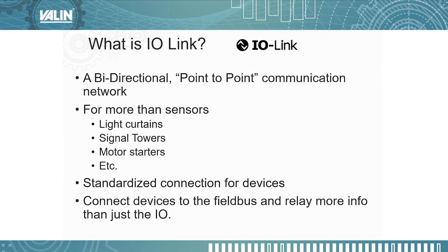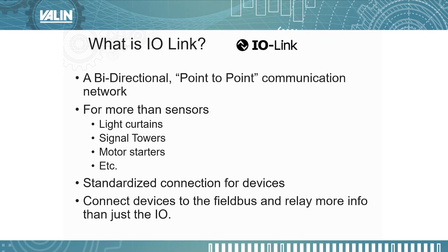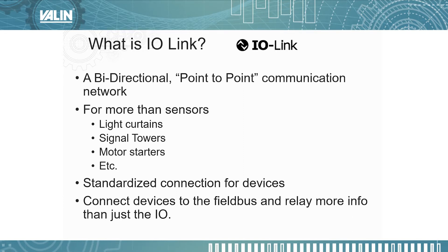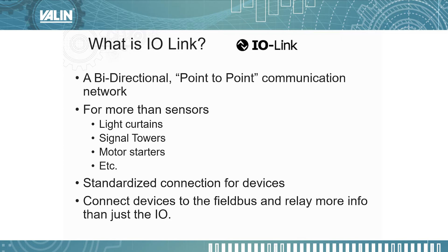So what is IO-Link? Basically, it's a bi-directional point-to-point communication network — meaning it communicates from the device to a master and from the master to the device. It's traditionally thought of as being used for sensors such as inductive sensors or photo sensors, but it can also be used for light curtains equipped with an IO-Link interface, signal towers, motor starters, relays, etc.